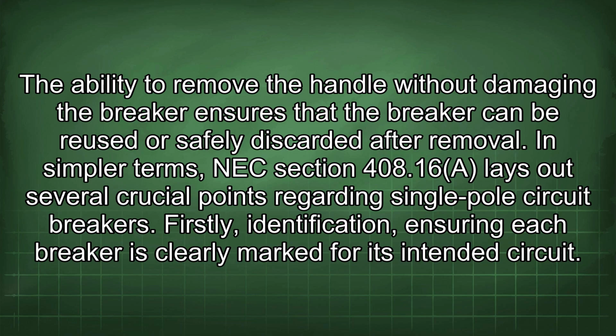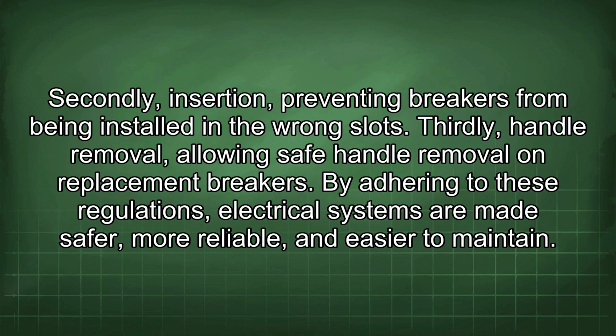discarded after removal. In simpler terms, NEC Section 408.16 lays out several crucial points regarding single-pole circuit breakers. Firstly, identification, ensuring each breaker is clearly marked for its intended circuit. Secondly, insertion, preventing breakers from being installed in the wrong slots. Thirdly, handle removal, allowing safe handle removal on replacement breakers.